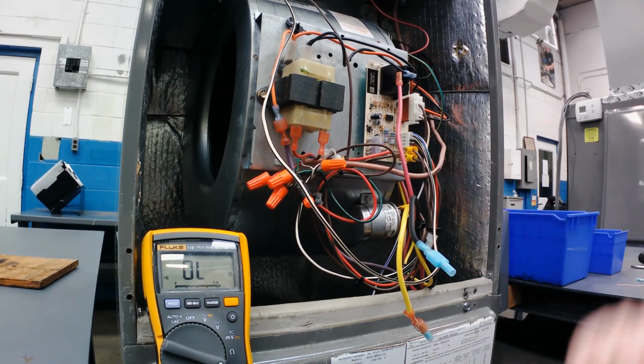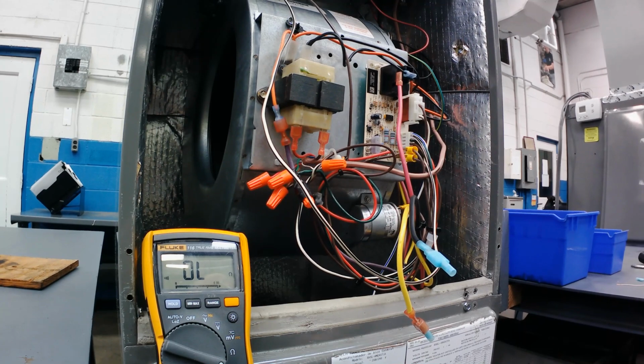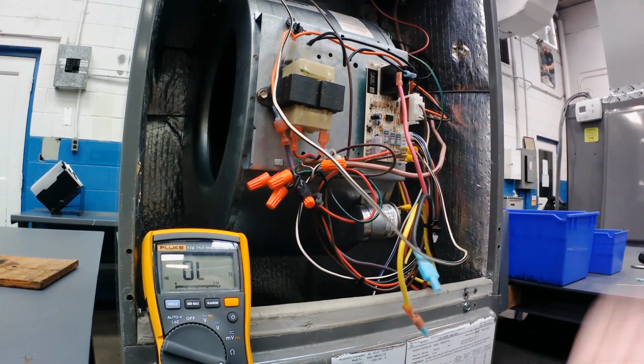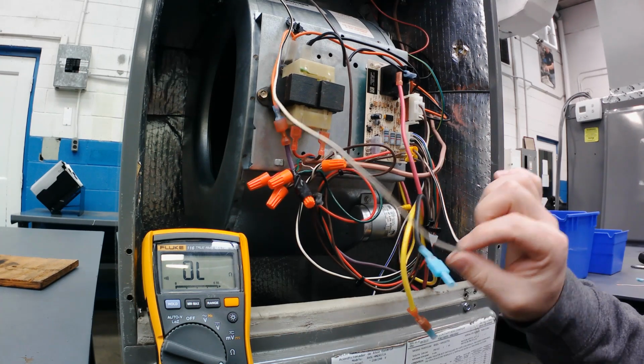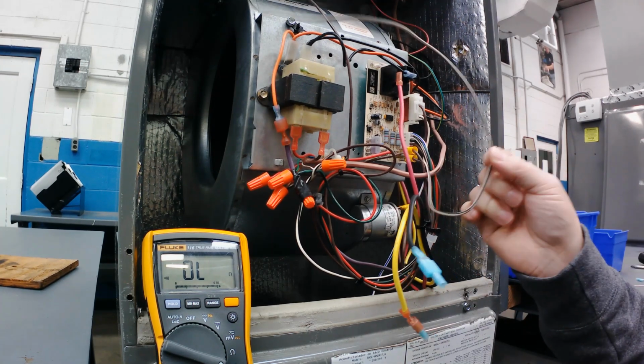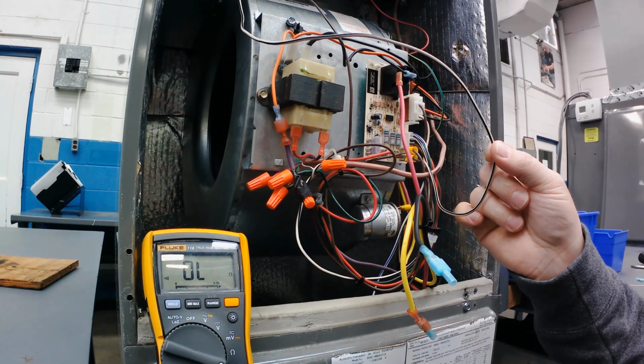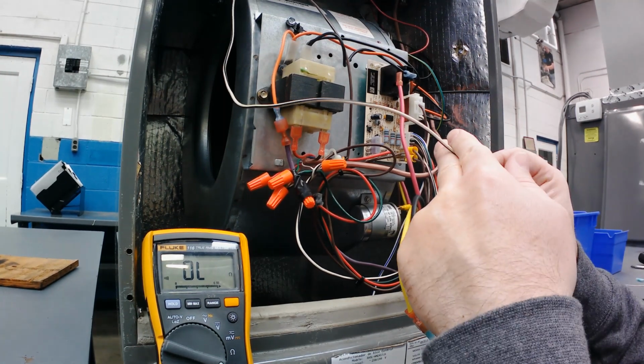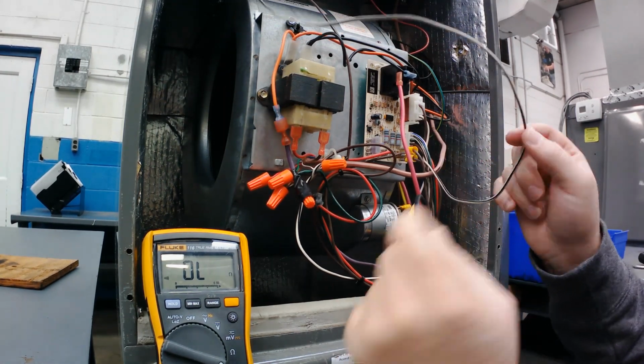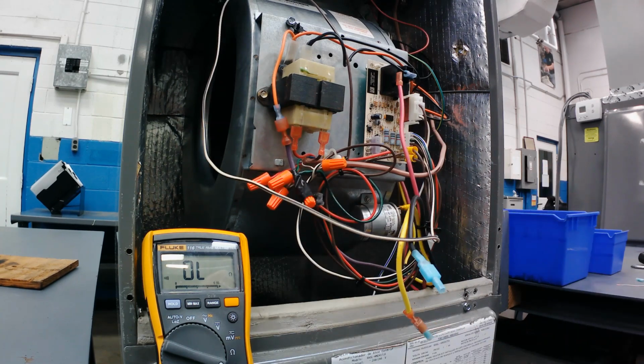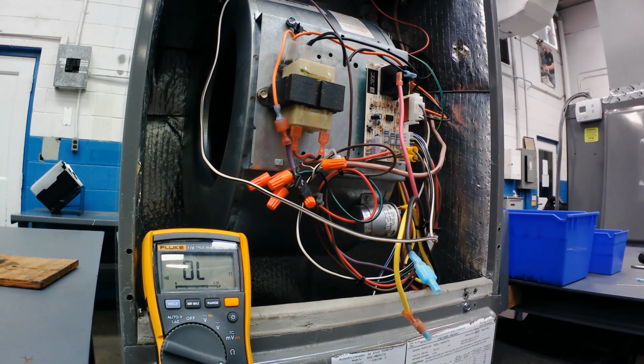I could put some terminals on it and make it look good if I had to, because the boards are essentially the same. The only thing that doesn't work on the Goodman board, or isn't there, is the W. And I could easily cut this, strip it back, and put a wire nut connection to the W wire coming out of the thermostat. So it's fairly simple, but hopefully you get the idea. It's another air handler board, so they're all meant to control the fan.